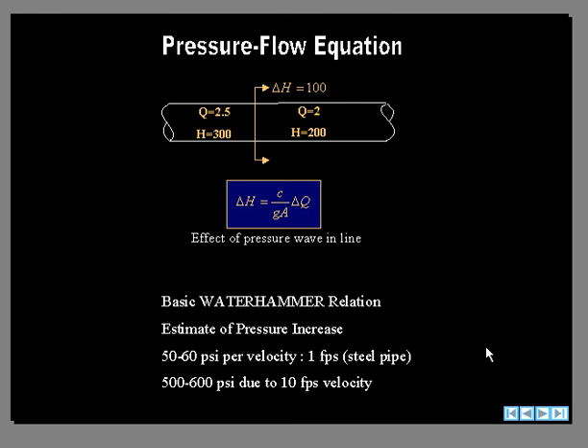And down here, this gives you an idea of what sort of pressure change accompanies a flow change. In a steel pipe, a one foot per second change in velocity will produce a 50 to 60 psi wave. So that's quite a large wave, and that's what is so significant.